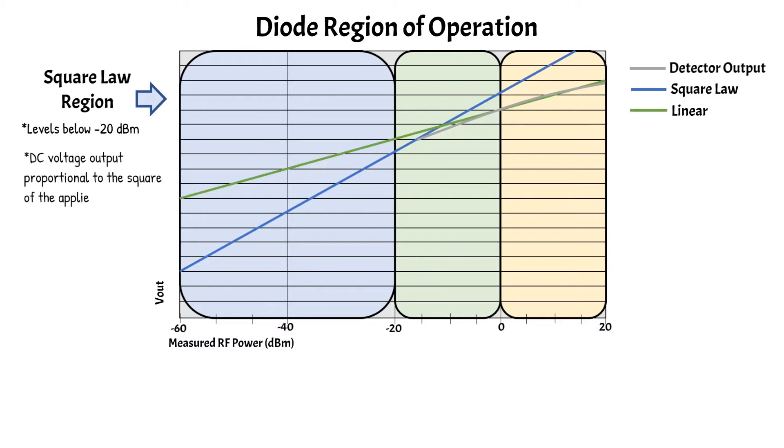The relation of the DC voltage to the power measured is dependent on the diode region of operation, which is typically separated into three sections. The square law region occurs at levels below about negative 20 dBm, where the diodes produce a DC voltage output that is closely proportional to the square of the applied RF voltage. This region is also modulation independent.